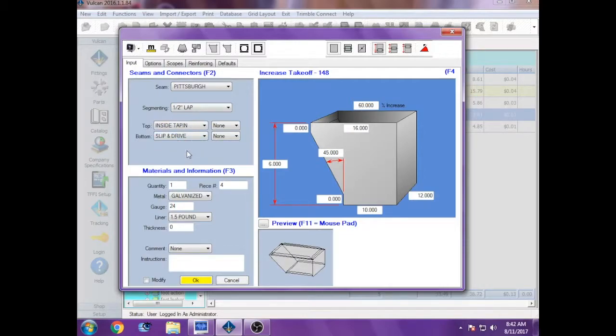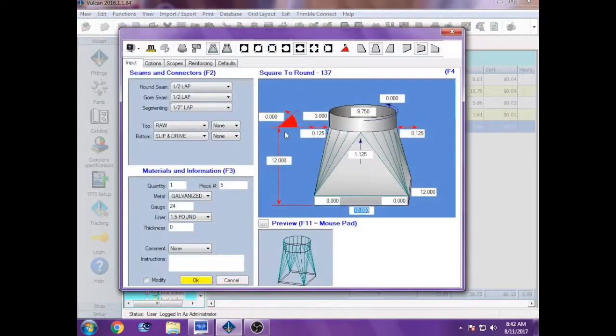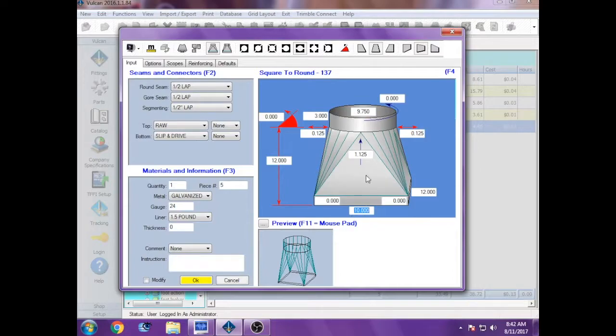The last one I entered in was a square to round, pretty much standard dimensions. The only difference is the round dimension has to be one quarter of an inch smaller than the intended. So if they say they want 10 by 12 to 10 inch round, it'll actually be 10 by 12 to 9.75, which is one quarter of an inch smaller.